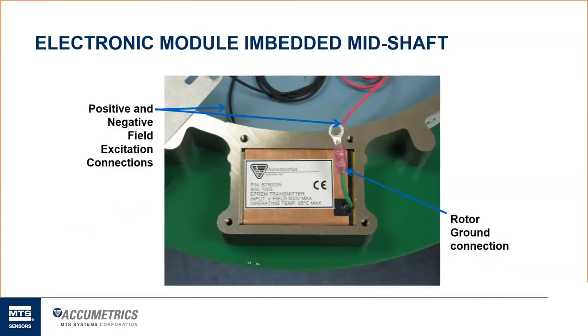This is the electronic module that's embedded in the steel collar itself. We have to make connection to rotor ground. So as I was explaining before, to accurately measure the field resistance and field voltage, we have to make contact to the negative side and the positive side of the field, as well as rotor ground. So we use the steel collar itself to get that rotor ground connection. That has to get mounted directly to the shaft, a very tight-fitting application, so that it's a reliable electrical ground connection. And then on the other side is where the positive and negative leads run off onto the board itself and make that contact. We'll go into a little more detail on that.